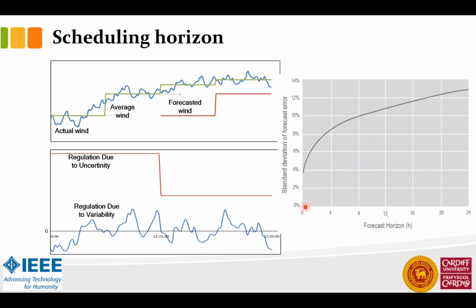Just spinning with a lot of extra capacity so that they can change their output where your requirements are. So even if you do it pretty real time, there is a forecasting error, that's what you are showing here. But if you try to do it like right now, Sri Lanka has day ahead scheduling of power plants. In that case, your solar or wind power plant's error could be as high as 12%. That means a 100 megawatt wind farm, you may predict it as 100 megawatt, but what you are producing actually could be only 88 megawatt. So you can see that 12 megawatt has to come from somewhere. That is what we call the regulation.